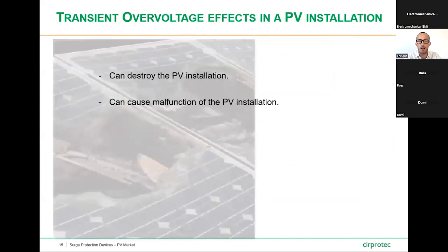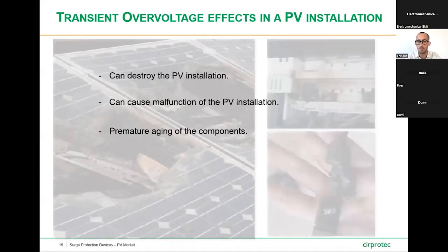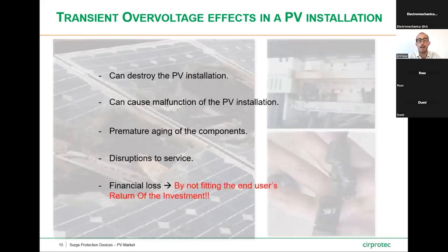Which are the transient overvoltages effects in a PV installations to take care about? Transient overvoltages can destroy directly the PV installation, can cause malfunction of the PV installation itself, can generate premature aging of the PV installation components, can launch disruptions to service, and the main important one, can generate financial loss by not fitting the end user's return of investment. That is the key why the end users are focused to install PV into their infrastructures.